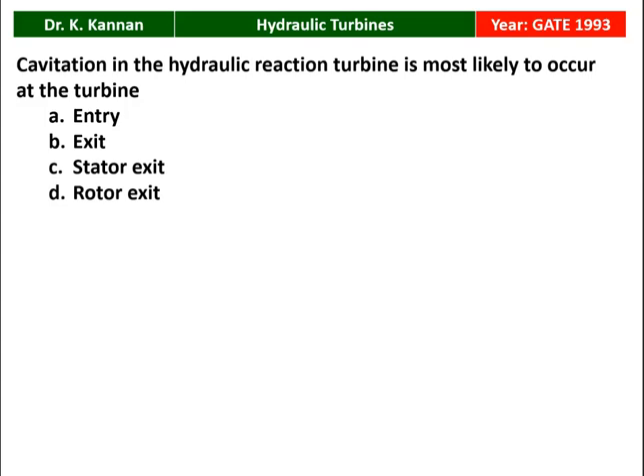Cavitation will occur. Cavitation is the formation of water bubbles or air bubbles in the flow. This is due to the change in pressure and temperature conditions in the hydraulic turbine. Normally in the hydraulic turbine, cavitation will occur at the rotor exit, whereas in the centrifugal pump it will occur at the entry where the pressure is very low.